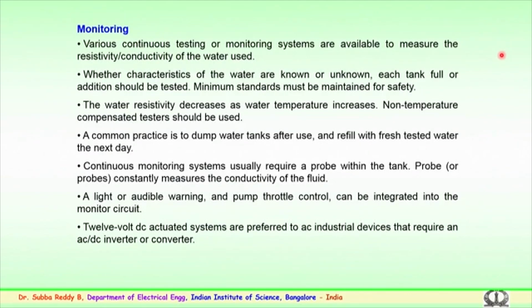Next is the monitoring of the cleaning systems. This is an equally important aspect for the utility engineers. Various continuous testing or monitoring systems are available to measure the resistivity or the conductivity of the water being used. Continuous monitoring is essential to check for better performance. Whether the characteristics of the water are known or unknown, each tank full or addition should be tested, because at any time contaminants could affect the water. So, the water has to be tested before it is used, and the minimum standards must be maintained for safety while using the cleaning methods, either in energized or de-energized conditions.